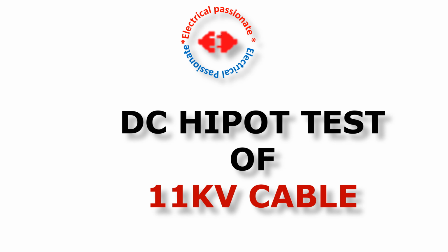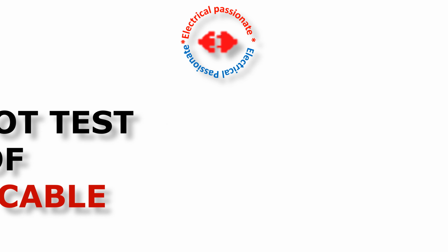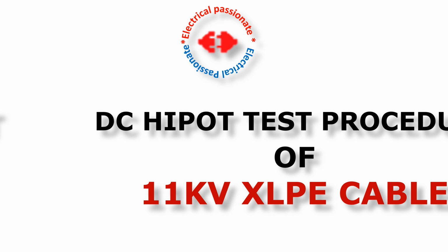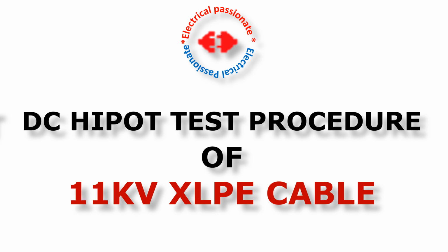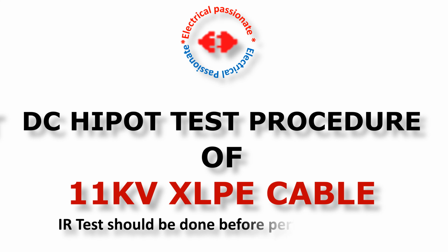Hipot testing can be done by using AC, DC or very low frequency VLF test voltage. We shall also discuss AC and DC Hipot testing and the parameters that need to be considered while selecting the AC/DC Hipot test kit for a particular test object. The DC Hipot testing procedure of an 11 kV cable will be shown here. Before the test, the IR test, insulation resistance test, should be done and recorded for further analysis.